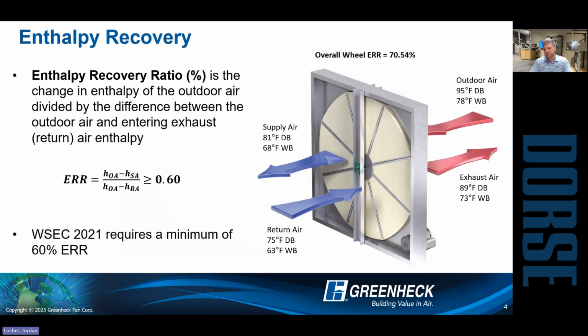One of the big differences we see is enthalpy recovery versus sensible recovery. For Greenheck, our focus is on enthalpy recovery. The metric that we're using here is ERR, or enthalpy recovery ratio. One of the bigger changes to the Washington Code is they did adopt an enthalpy recovery minimum. That minimum is 60% ERR. You can see the equation for ERR: it's just the change in enthalpy of the supply air over the change in enthalpy of the return air.